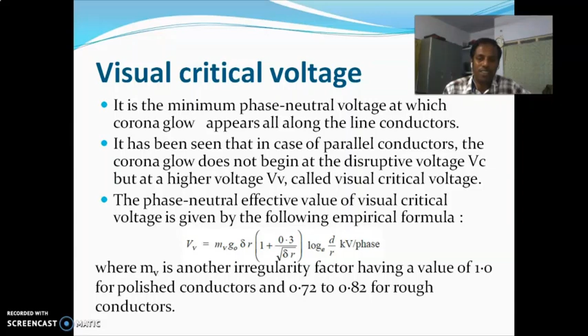So this visual voltage will be determined by the formula mv G0 delta r into 1 plus 0.3 divided by square root of delta r, log of D by r kV per phase. So we know these terms, G0, delta, r, all values are same. The mv is the irregularity factor for visual critical voltage. So the value is 1 for polished conductors and 0.72 to 0.82 for rough conductors.